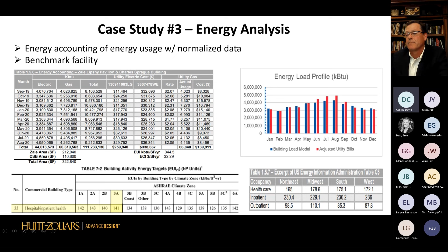We went to the manufacturer of the chillers and got the performance load data. We were able to generate and see how much kW they're actually using a year for the cooling plant, and that's at 3.6 million kWh. The ton hours came from our calcs, and we came up with a performance of 0.813 kW per ton, which is pretty good.